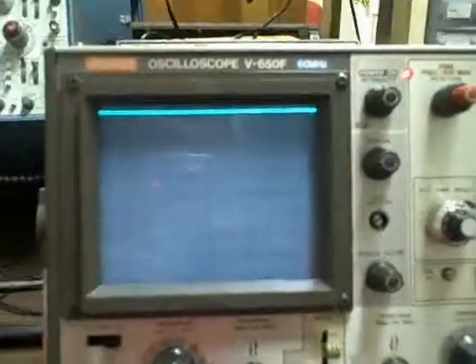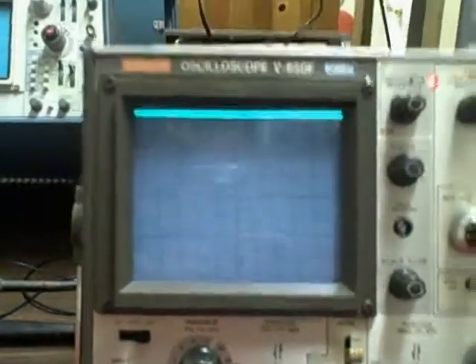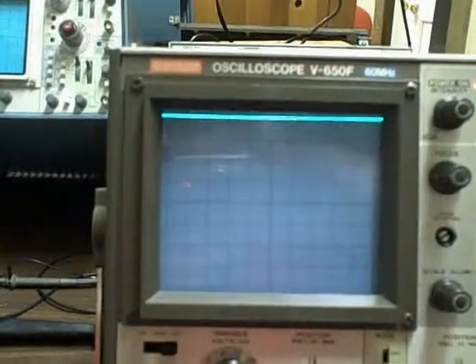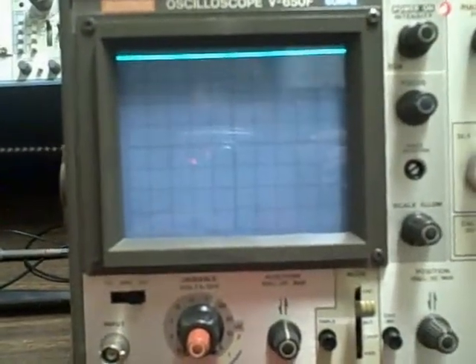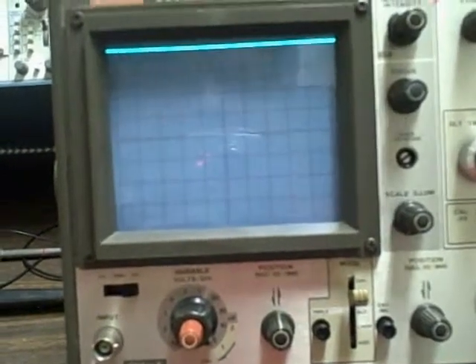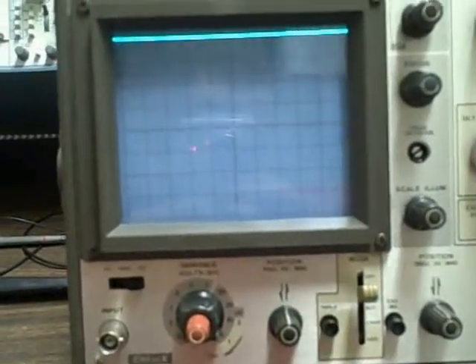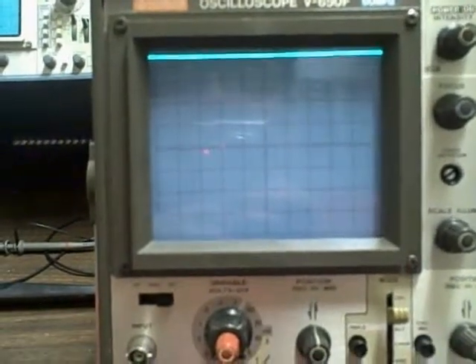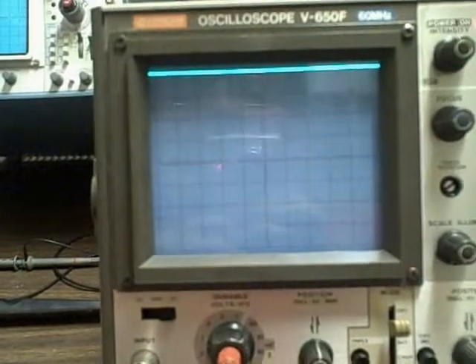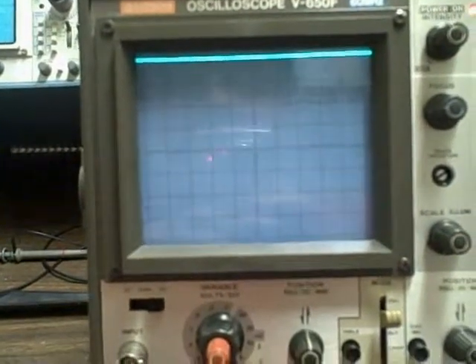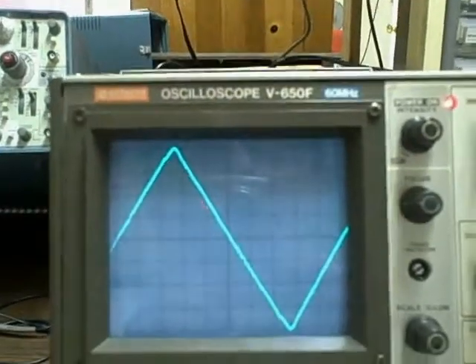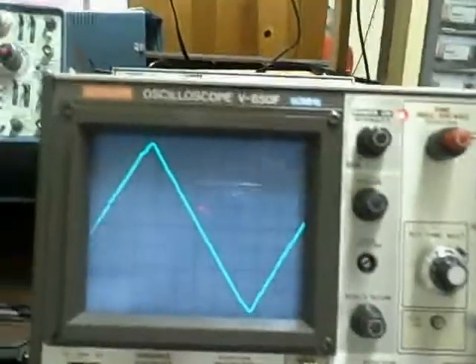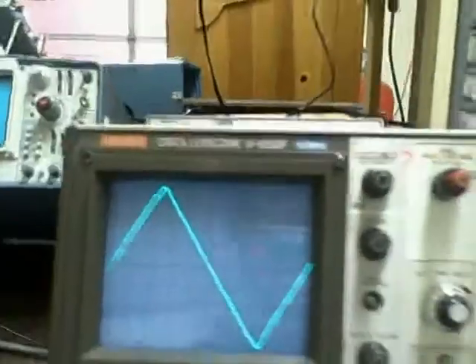So, okay folks, the point is we've been able to read the voltages accurately and display them accurately on the division scale. So we know we can read the voltages. If we can get our time base right and we provide a linear ramp signal, then we know that we're able to read our voltages in between. We're faithfully reproducing the signals as they come in. So let's check our time base at a couple of other speeds and see how we do.